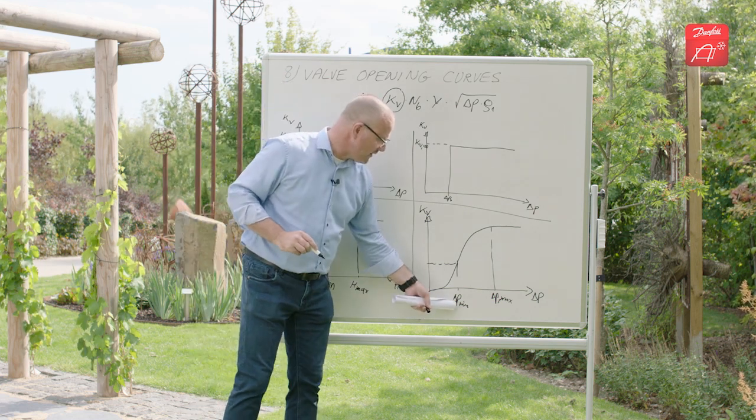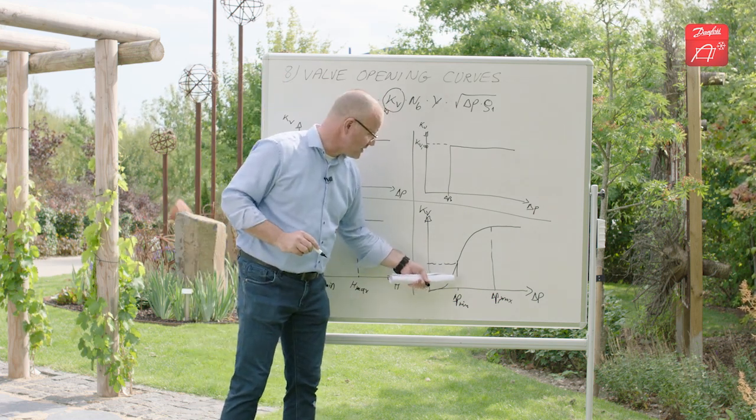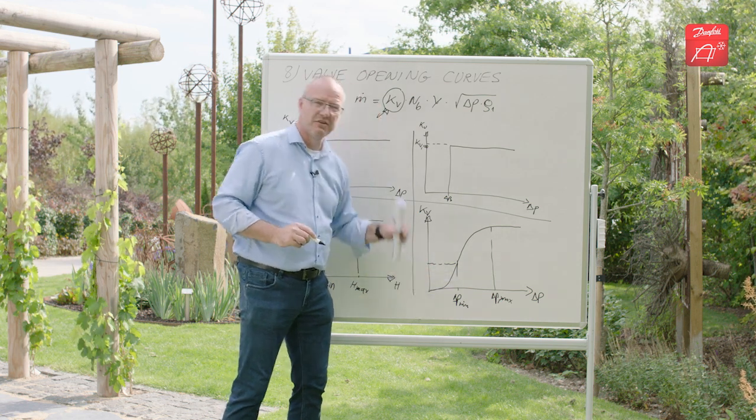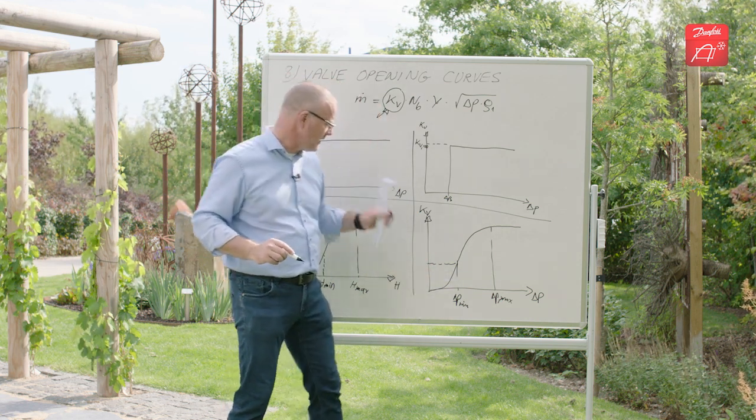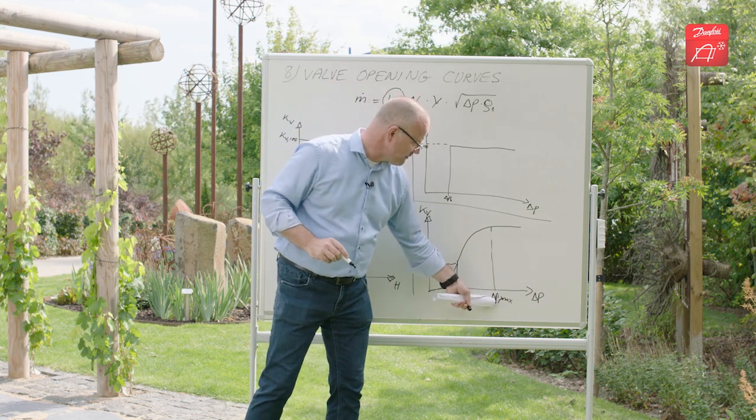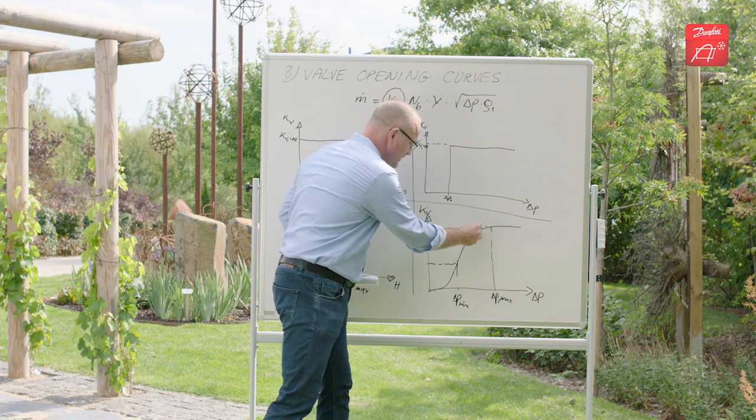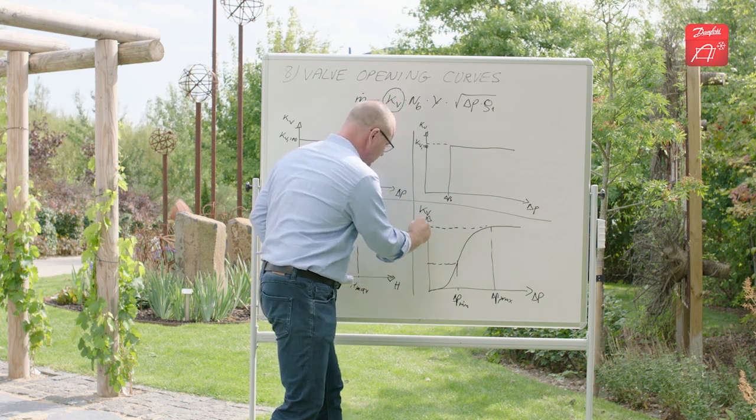Again, we have a minimum pressure drop below which we do not recommend to operate the valve. If you go below this, you have a chance of valve fluttering. We have a maximum pressure drop at which the valve is fully open. So here we have the fully open kV value.